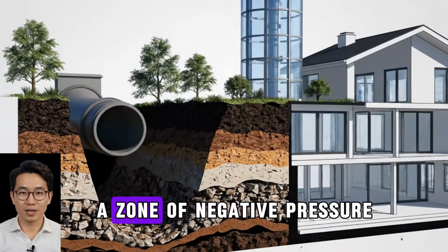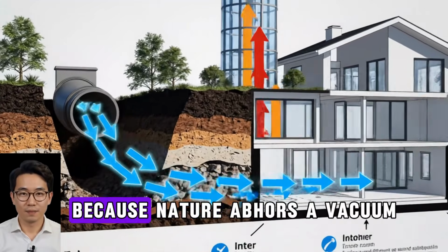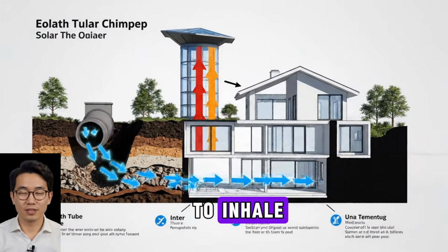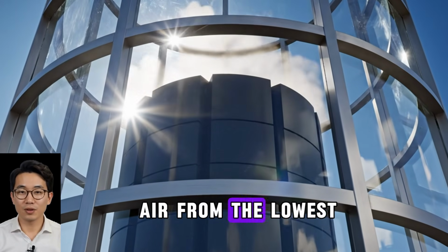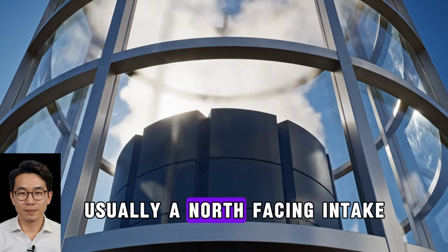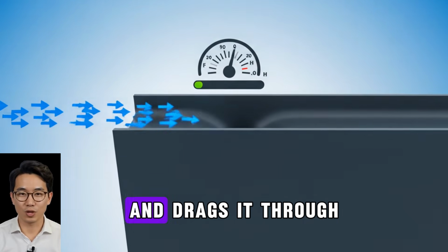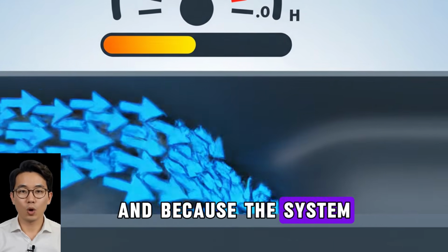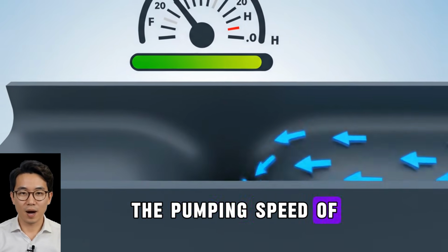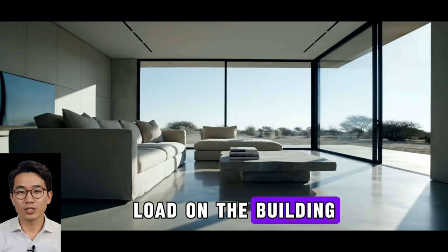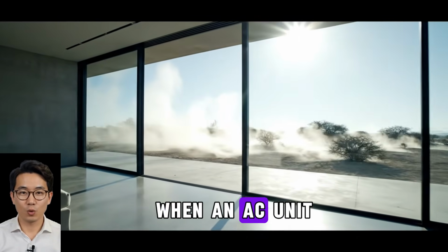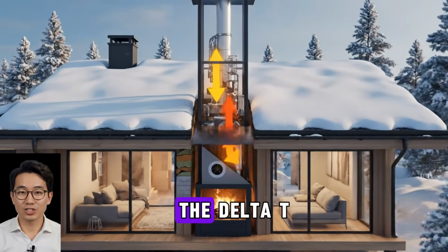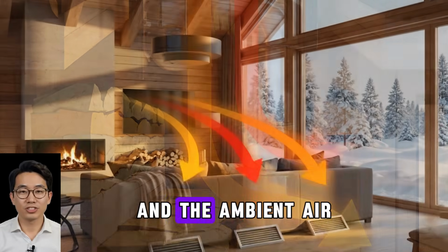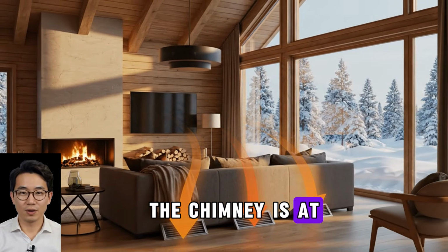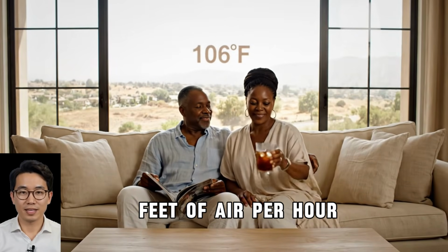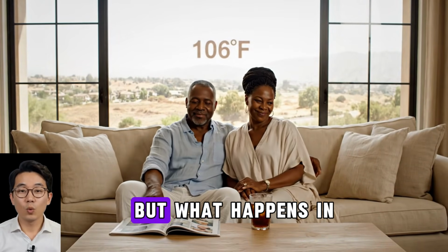This upward movement creates a zone of negative pressure at the base of the chimney. Because nature abhors a vacuum, the building is forced to inhale. It pulls fresh, cooler air from the lowest, most shaded part of the building, usually a north-facing intake or an underground earth tube, and drags it through the living spaces. And because the system is powered by solar radiation, the pumping speed of the chimney is in direct proportion to the heat load on the building. On a 100-degree Fahrenheit afternoon, when an AC unit is struggling and drawing maximum current, the delta T, the temperature difference between the collector and the ambient air, is at its peak. The chimney is at its most powerful, moving thousands of cubic feet of air per hour without moving a single mechanical part. But what happens in the winter?